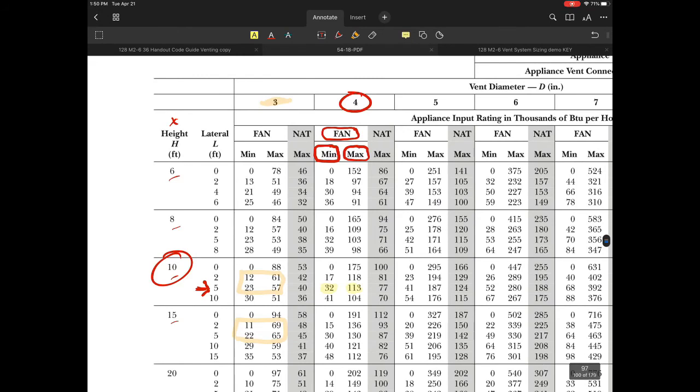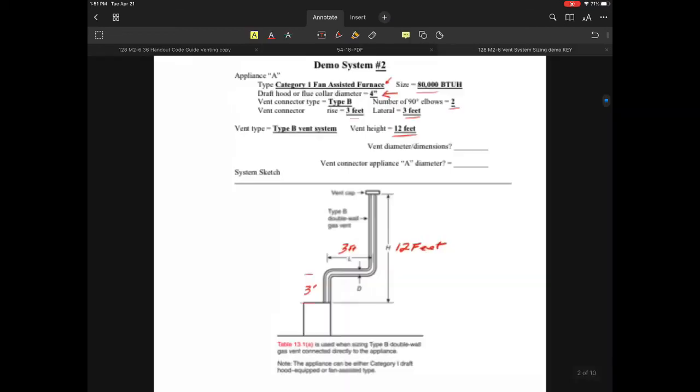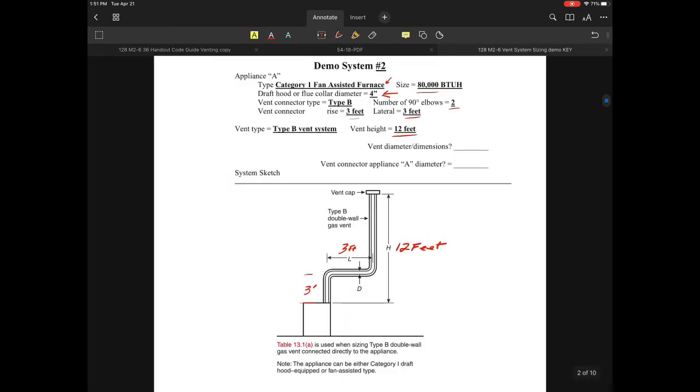For an 80,000 BTU system, this is very simple. We're definitely dealing with a four-inch vent system. No interpolation needed, no concerns whatsoever, no chance of downsizing because the appliance outlet was ideal.